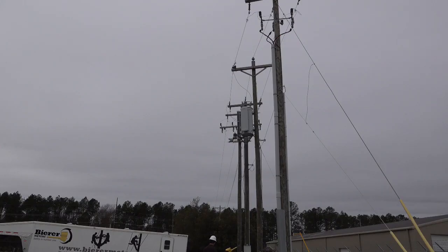In our last demonstration, the VD1000 is going to be used on a correct overhead build. Notice our portable training trailer to the left. That's a 40-foot trailer, so this line is roughly 40 feet above Earth. With the VD1000 in the OH position, we'll compare the reading above Earth on this demonstration versus the overhead demonstration at a lower height. I'll speed the video up a little bit so it doesn't take so long for us to get our reading.